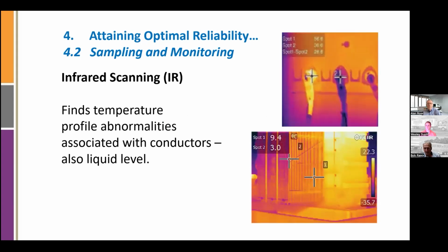Infrared scanning, taking a look at the transformer from a thermal point of view, finds temperature abnormalities. The two that I'm showing here on this screen: one is an overheated conductor, and the other would be level. You can see level. Again, if the transformer has a low level, the transformer is going to overheat, and you'll see that in the profile.